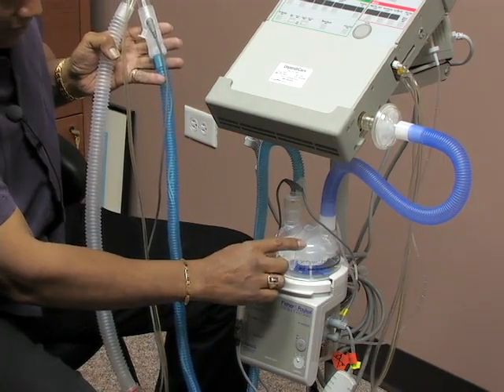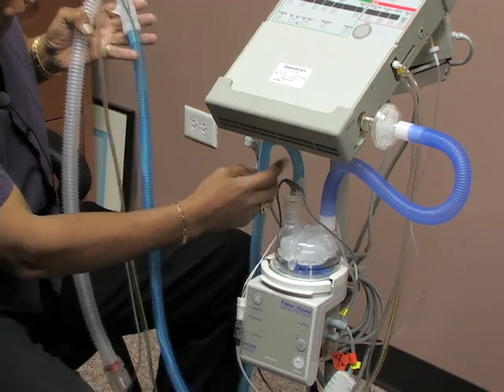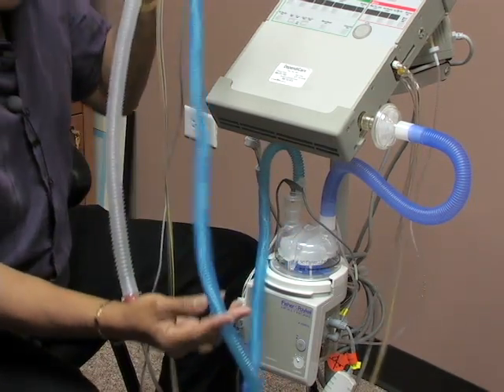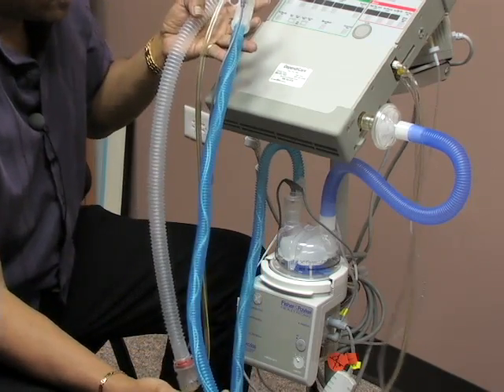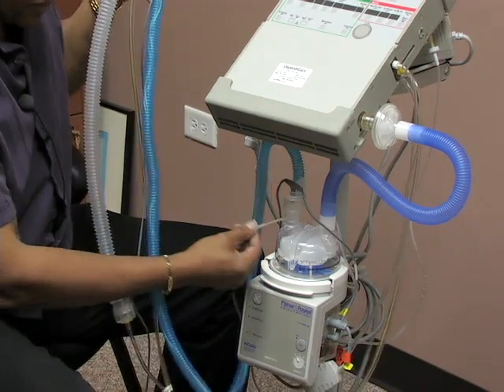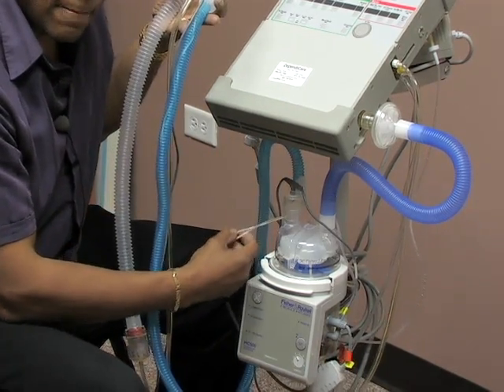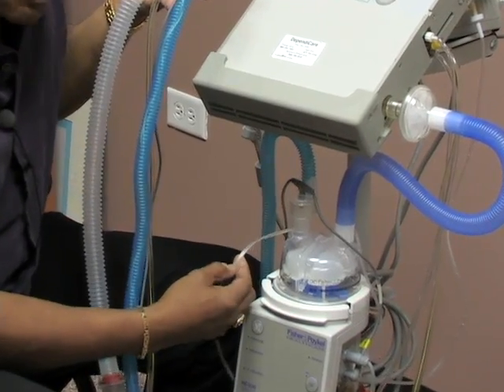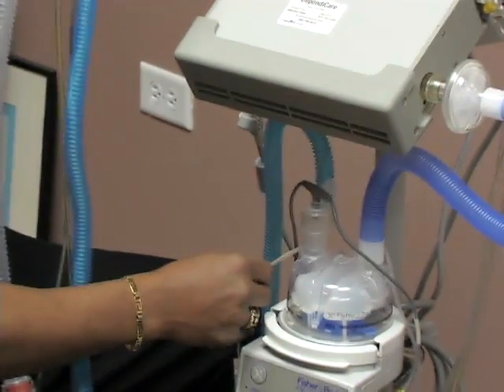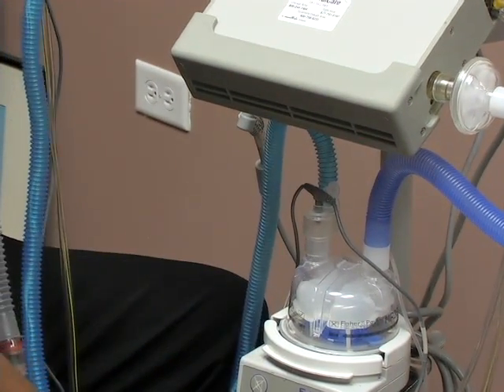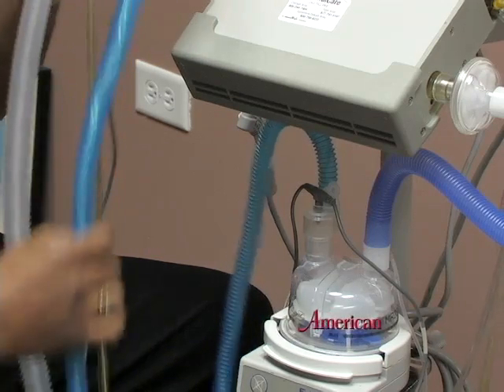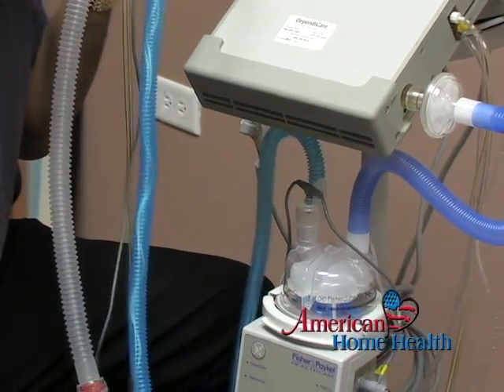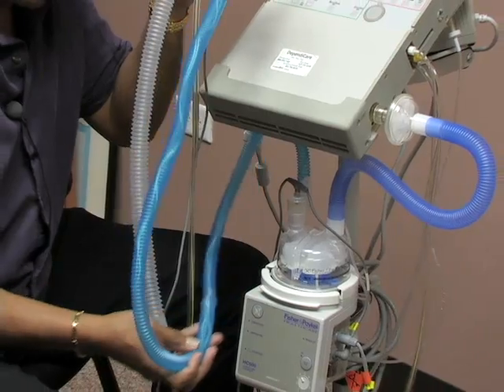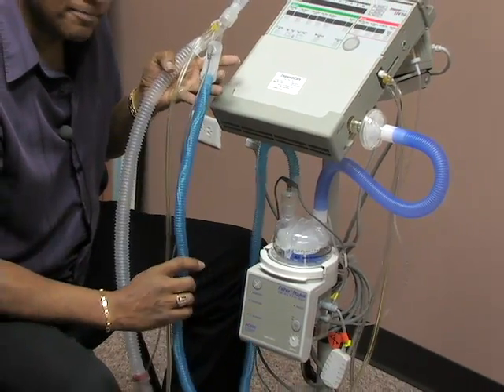The humidified air comes up through the wet side, and in this wet side there is what's called a heating circuit or heating coil. This heating coil, the purpose of it is to maintain the humidified air in this humidified form and to prevent condensation. Condensation is the last thing we want because condensation in your line pooling breeds bacteria.